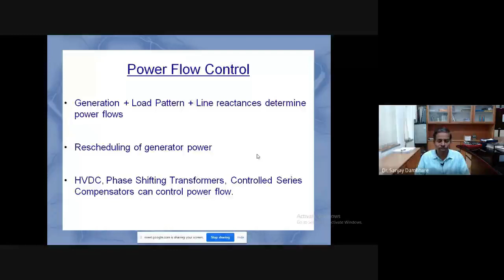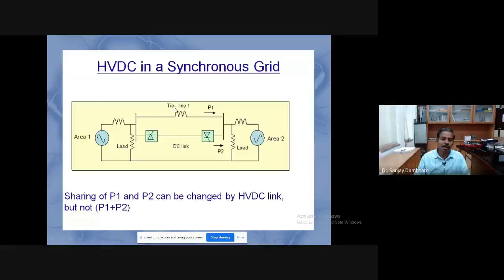You can reschedule the power flow by phase shifting transformers, or by the series compensators, or HVDC can be used. In fact, FACTS devices can be used effectively to control the power flow. So this is how the power flow in this transmission line can be rescheduled, right? And the power flow can be controlled, provided you have an HVDC link or the FACTS controller introduced in this.